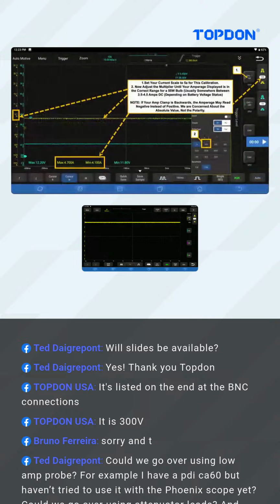On the slide, after I set it up, you can see my clamp connected and the scale set up. We have the multiplier set, set to the probe type - probe type should show current. I've got it toggled wrong in the picture, but it's supposed to show current. Then we play around with the multiplier until the scale is correct and the minimum and maximum we're measuring on the channel matches what that 55 watt bulb should be drawing for current.